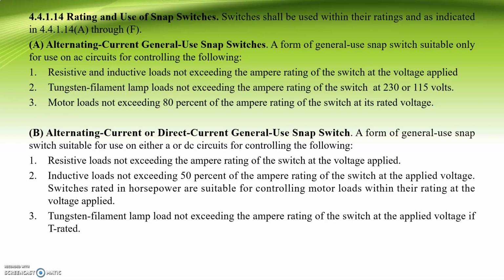B, alternating current or direct current general use snap switch. So a form of general use snap switch suitable for use on either AC or DC circuits for controlling the following. So first, resistive loads not exceeding the ampere rating of the switch at the voltage applied. The second is inductive loads not exceeding 50% of the ampere rating of the switch at the applied voltage. So switches rated in horsepower are suitable for controlling motor loads within the rating at the voltage applied.